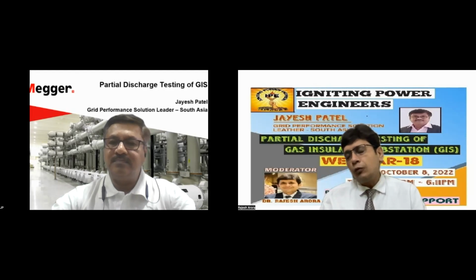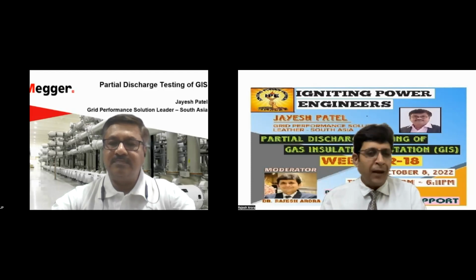The only option left is to go with the GIS, which needs only 20 to 25% of the area or space required as compared to AIS. Last but not the least, by physical inspection, it is not possible to pinpoint any fault or sparking, etc. in the GIS. The only monitoring devices available in the GIS are the gas pressure of different modules and compartments that can be monitored. Therefore, PD sensors are provided by all OEMs for PD monitoring.